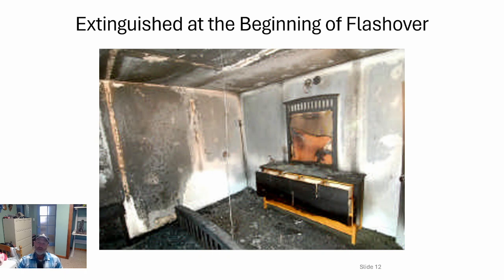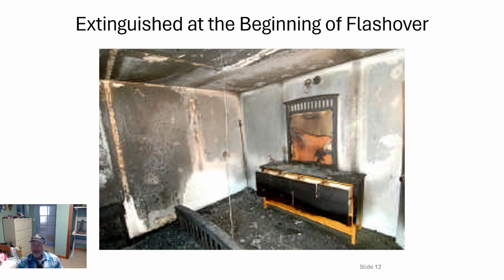Here's a similar situation — a first floor ranch-style home test. The fire origin is on the far left of this picture. In this case, they suppressed the fire immediately at the time of flashover. Then they ran the exact same test again, extinguishing the fire two minutes after flashover, simply to illustrate the principle of ventilation. They had a door on the right side. Observe the closed cabinet — it doesn't have any damage.